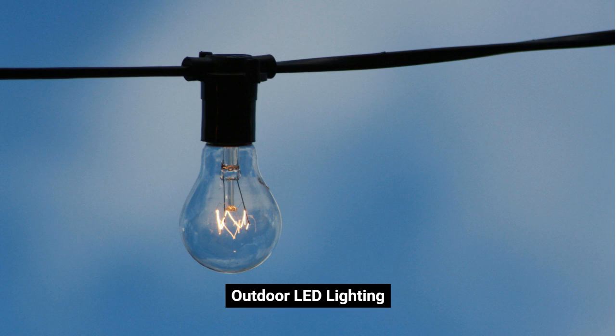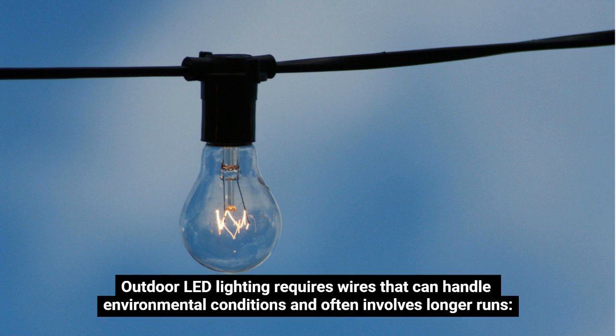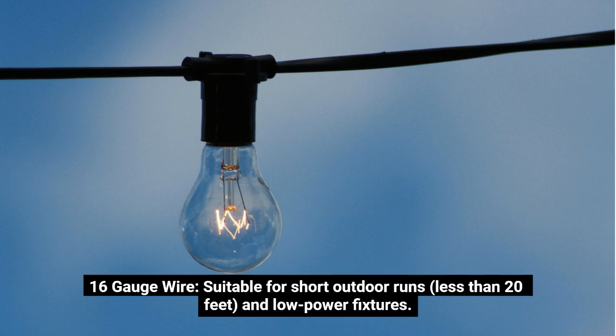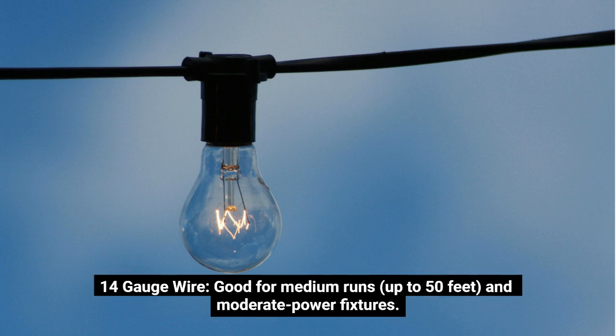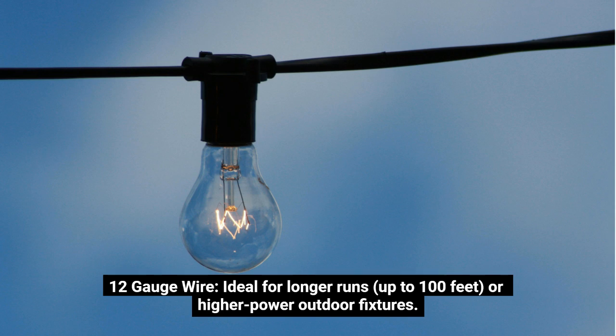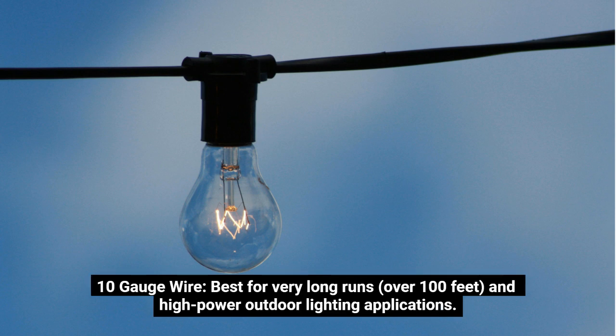Outdoor LED lighting. Outdoor LED lighting requires wires that can handle environmental conditions and often involves longer runs. 16 gauge wire, suitable for short outdoor runs, less than 20 feet, and low power fixtures. 14 gauge wire, good for medium runs, up to 50 feet, and moderate power fixtures. 12 gauge wire, ideal for longer runs, up to 100 feet, or higher power outdoor fixtures. 10 gauge wire, best for very long runs, over 100 feet, and high power outdoor lighting applications.